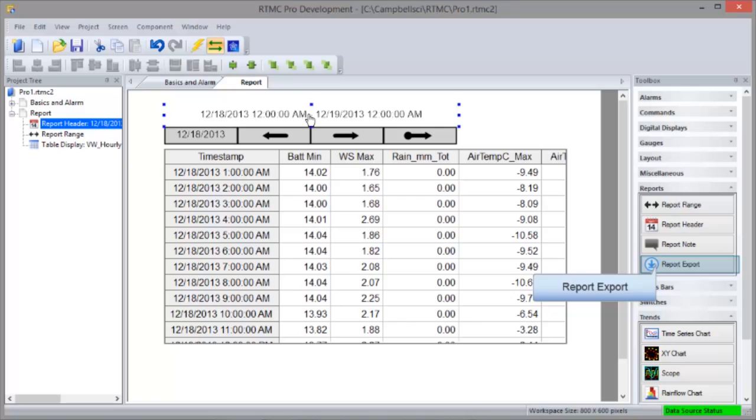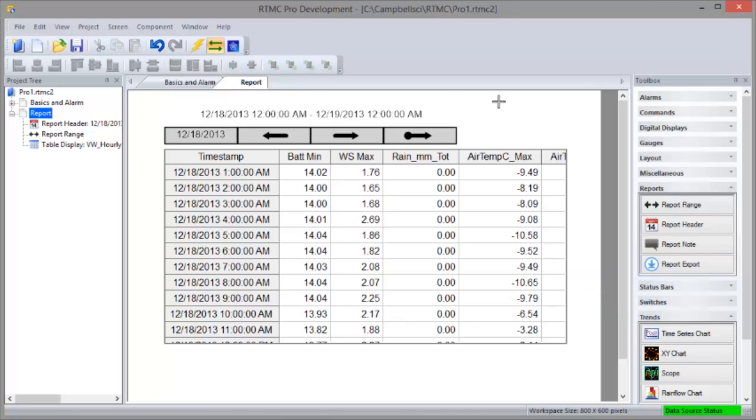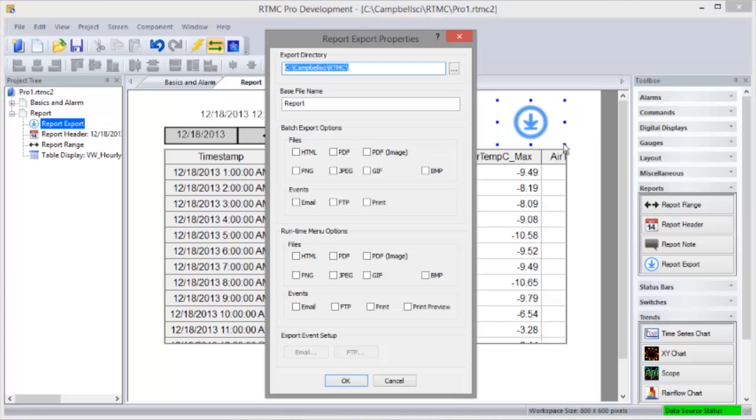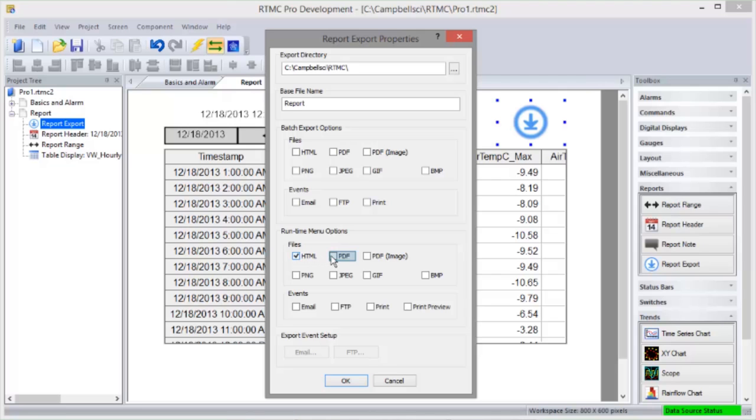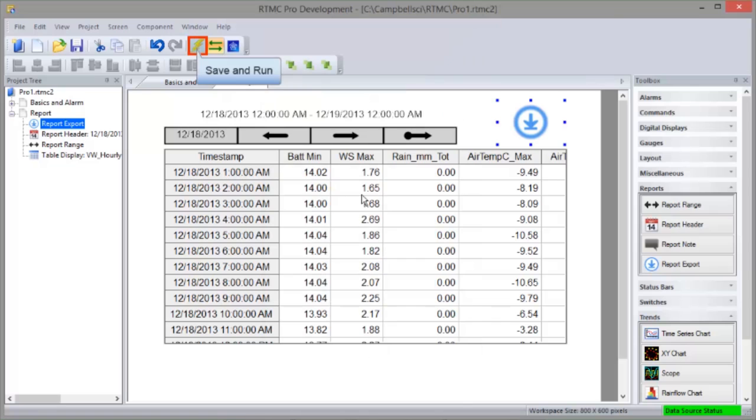When you've finished designing your report, you can specify how you want it to be exported. You can choose to have the report exported by running a batch file and or on demand from RTMC runtime. For both batch export and RTMC runtime, you can choose from a variety of file formats. You can also select events, email, FTP, print, to be triggered when the report is exported. We'll have another video tutorial demonstrating how the CSI web server sends your data to the internet for viewing. So for now, I'll just mention that when viewing a report on the web, the export events such as email, FTP, and print are not supported. Only PNG images can be exported. Let's see what this looks like in runtime.